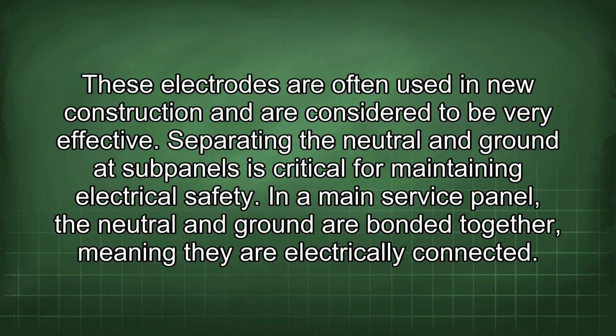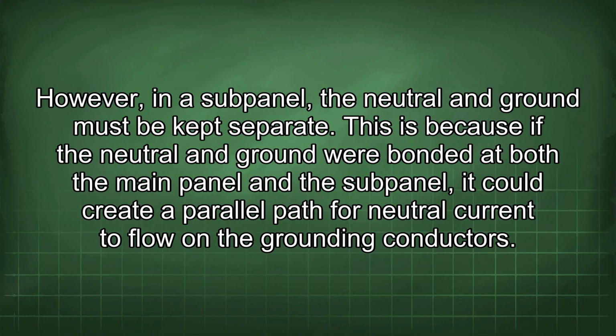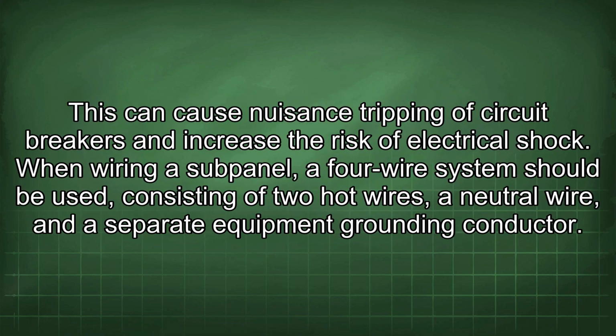Separating the neutral and ground at subpanels is critical for maintaining electrical safety. In the main service panel, the neutral and ground are bonded together, meaning they are electrically connected. However, in a subpanel, the neutral and ground must be kept separate. This is because if the neutral and ground were bonded at both the main panel and the subpanel, it could create a parallel path for neutral current to flow on the grounding conductors. This can cause nuisance tripping of circuit breakers and increase the risk of electrical shock.